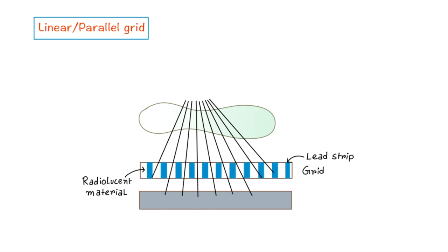Now if you see, the central rays of the beam are almost parallel. But the peripheral rays are divergent. So at the periphery, the divergent primary photons get cut off or get absorbed.